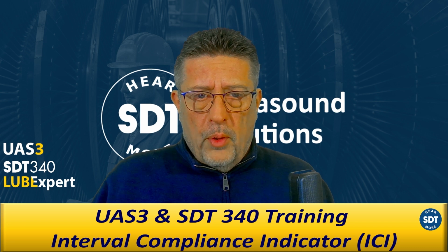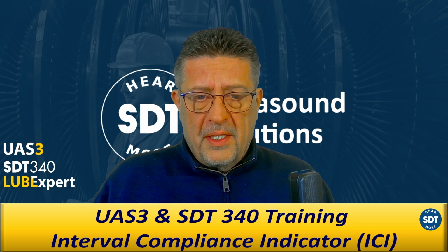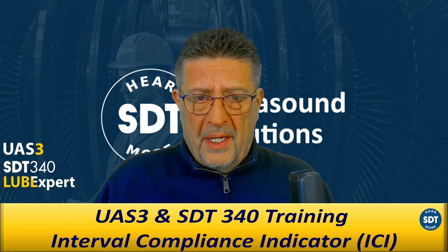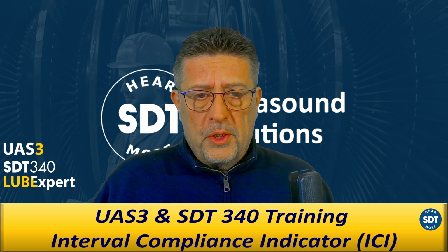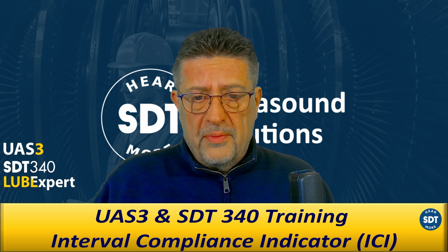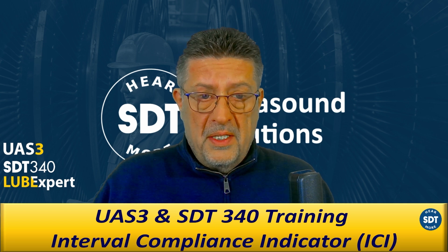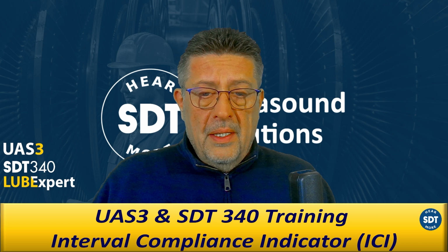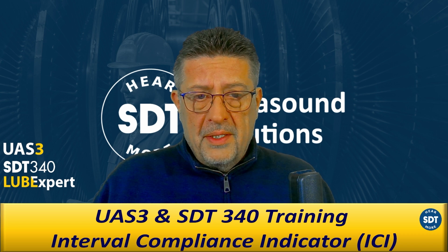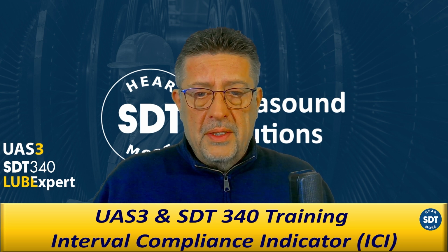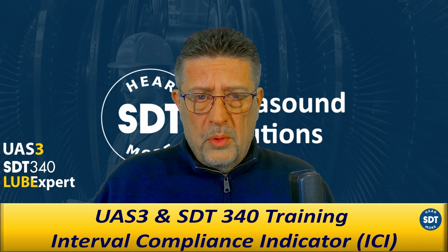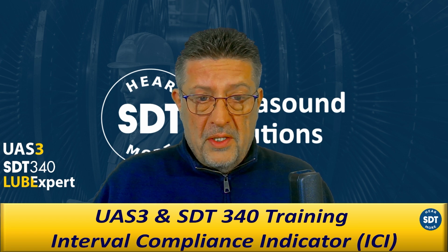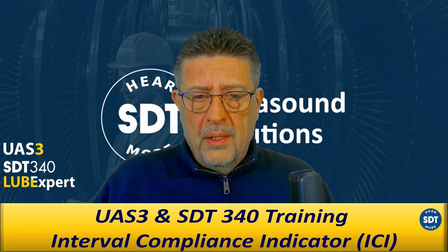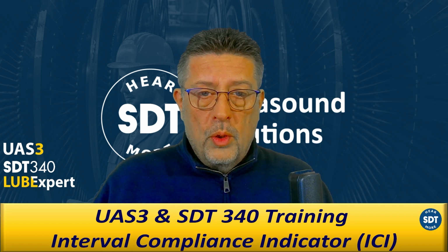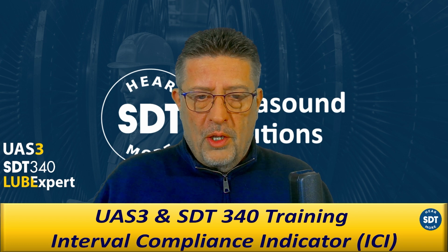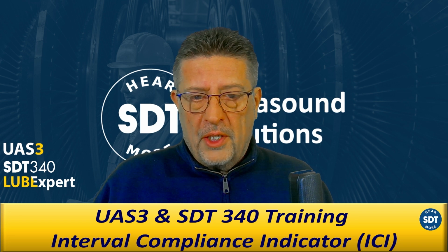Interval is a very important part of our settings in every condition monitoring practice. So interval should come as a result of a failure mode effect analysis and deep understanding of the failure. We are trying to collect data at a certain time, so we will be able to detect an onset of the failure as early as possible, but again, not too early, because it will then cause a lot of resources to be engaged in data collection.